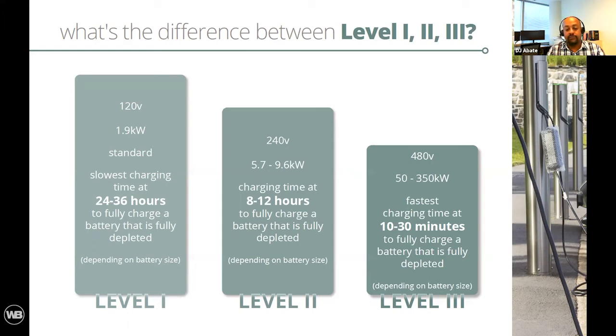Now when you go to level 3, because of the size I was discussing earlier, they range from 50 all the way to 350 kW. The breaker required is anywhere from 100 amp all the way to 600 amp. So we're talking about large breakers, which will not fit in your standard panel, and you need to install a switchboard just for those breakers. That's why level 3 requires a lot more planning than level 1 and level 2.